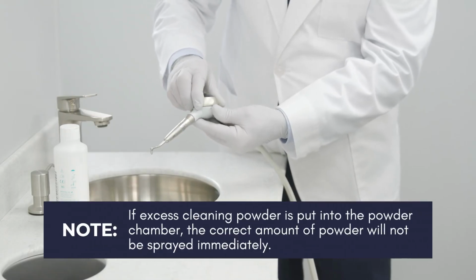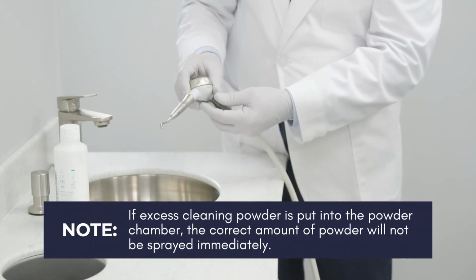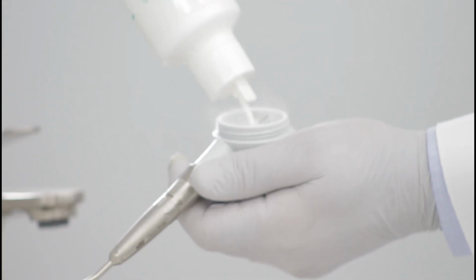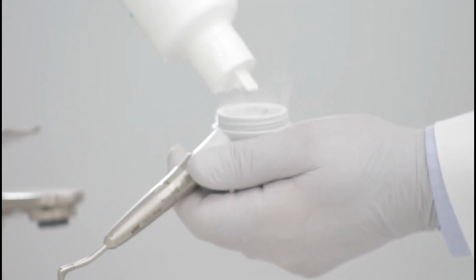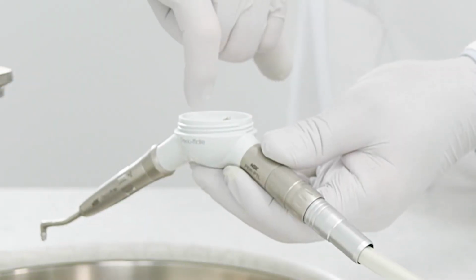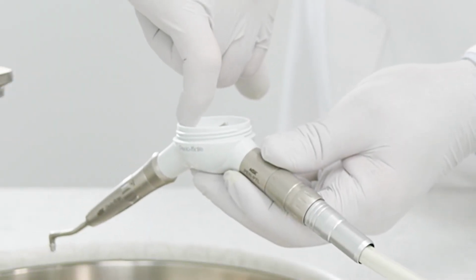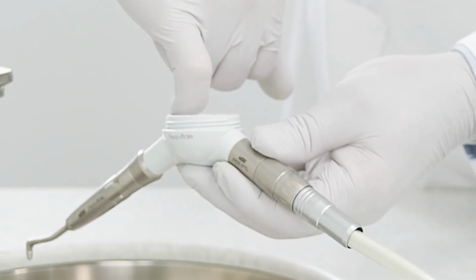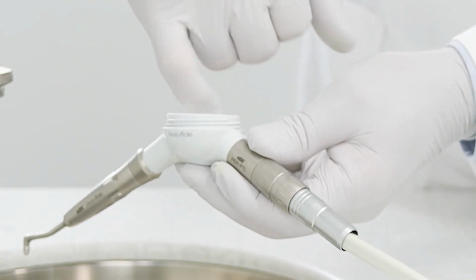Note: if excess cleaning powder is put into the powder chamber, the correct amount of powder will not be sprayed immediately. Fill the chamber slowly and avoid scattering the powder. Immediately clean any powder stuck inside the powder case or on the threaded portion of the powder case cap, or it will be difficult to close the cap.